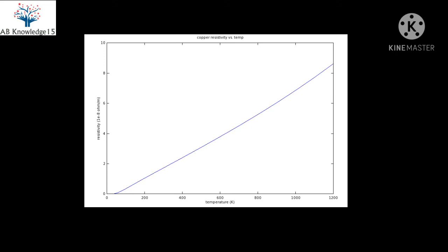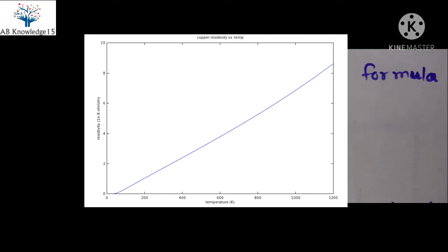Here I have shown one graph that shows the relation between temperature and copper resistance. It shows that copper resistance increases as the temperature increases. Transformer winding is made of copper and the temperature of the transformer will not be the same during every test. Due to this, the measured winding resistance needs to be converted to the standard temperature for comparison purposes.